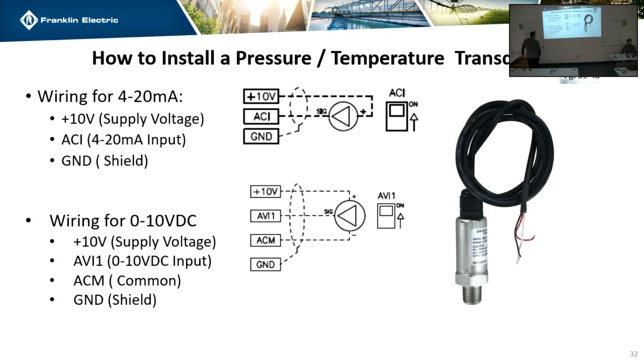All right, so just basic setups of how you would set up a pressure transducer or a temperature sensor. It's kind of straightforward. This is the same going to the drive or the terminal blocks. That's why we have it set up that way. It doesn't matter if you have a standalone drive or the panel, it's going to be the same.